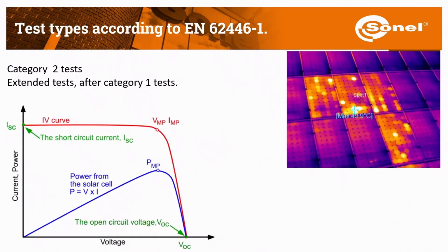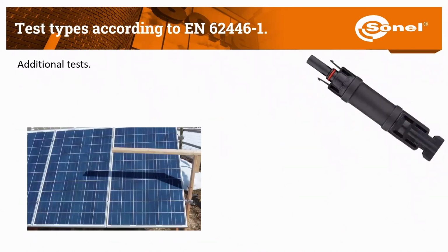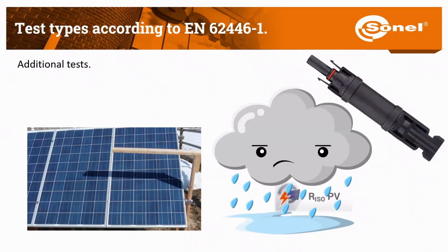Category 2, which is not obligatory, but it's also good to have, is to make the curve of the current and the voltage. However, SONEL products at the moment don't have this feature. Additional test says that the whole installation should be tested in the various conditions as well.